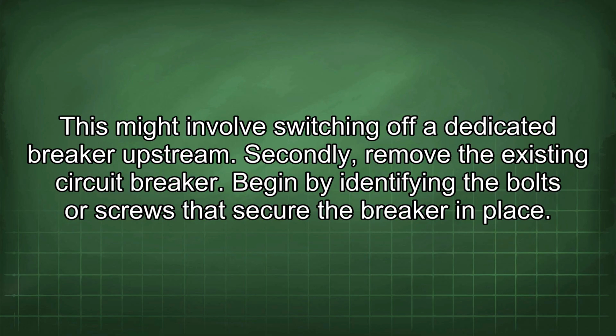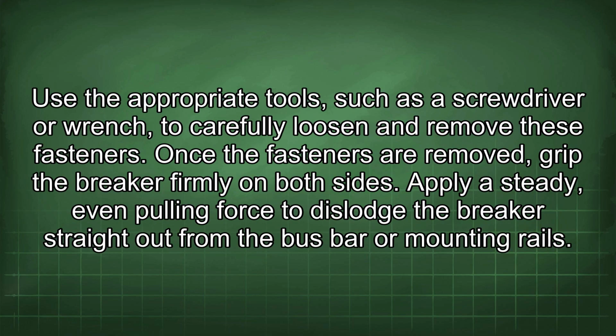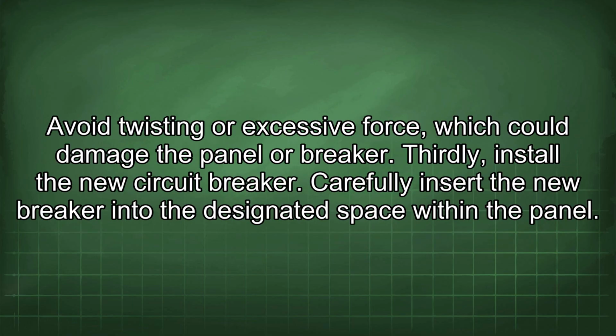Secondly, remove the existing circuit breaker. Begin by identifying the bolts or screws that secure the breaker in place. Use the appropriate tools, such as a screwdriver or wrench, to carefully loosen and remove these fasteners. Once the fasteners are removed, grip the breaker firmly on both sides. Apply a steady, even pulling force to dislodge the breaker straight out from the bus bar or mounting rails. Avoid twisting or excessive force, which could damage the panel or breaker.